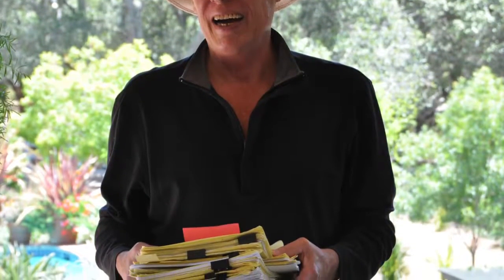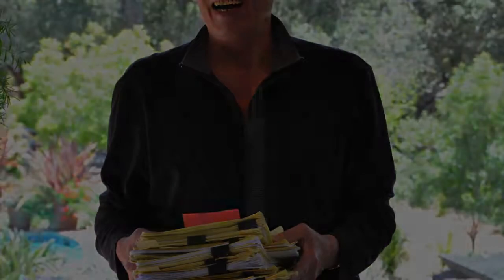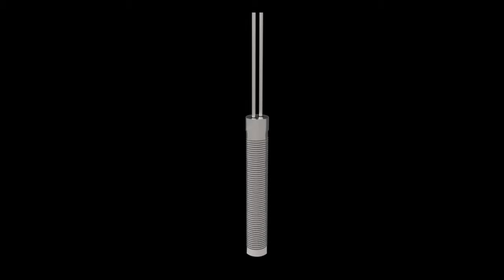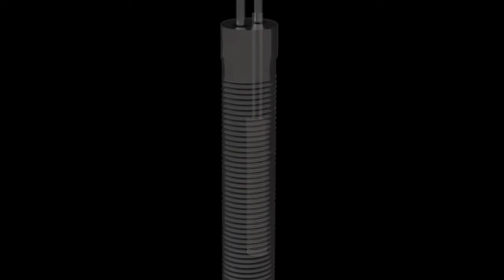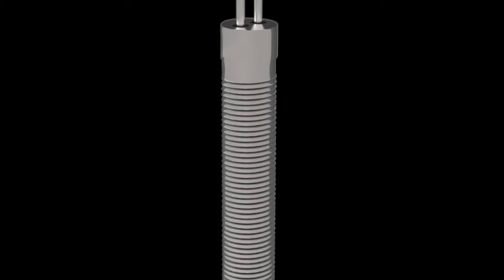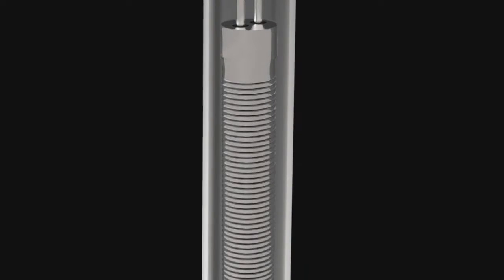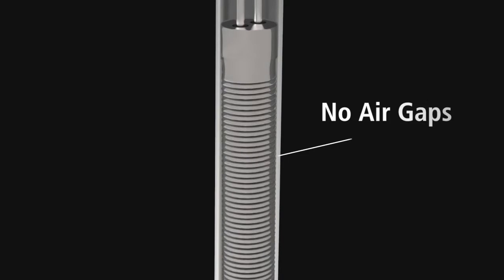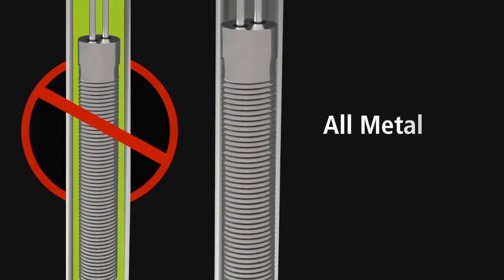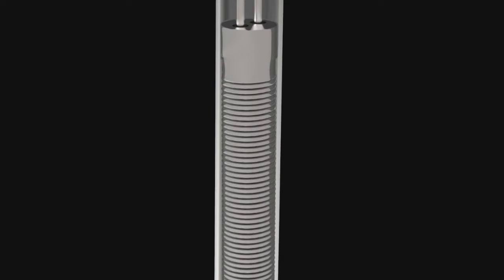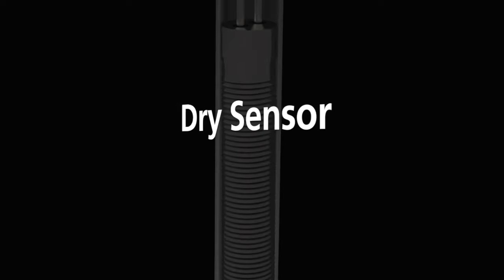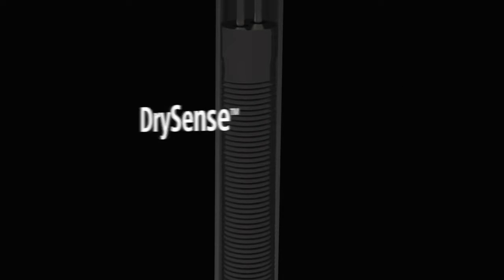After many years of experiments and testing, the answer finally revealed itself. On March 9, 1999, Dr. Olin patented a breakthrough thermal sensor design. Like other thermal mass flow sensors, it was made of a platinum resistance temperature detector wire wound around a ceramic mandrel. But this is where the similarities ended. Through a proprietary, highly controlled manufacturing process, a metal sheath is tightly formed on the mandrel and wire assembly to be in such intimate contact that no air gaps exist and no organic filler cements are needed. This new sensor was literally all metal. In contrast to wet sensor design, this innovative cement-free sensor is known as a dry sensor. It is patented by Sierra and is brand named DrySense.